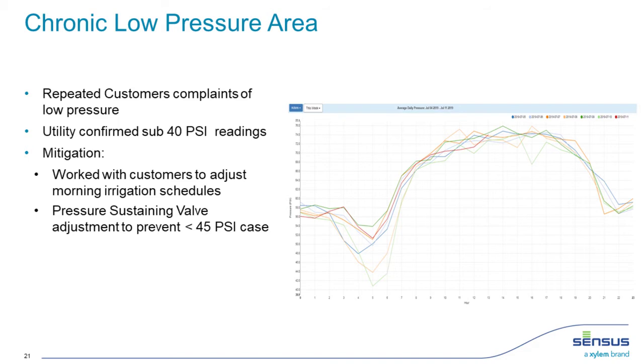What we were able to do to mitigate the issue was, first of all, to speak to a lot of the customers in that area. They had quite a few of their irrigation clocks set at the exact same time, and it turned out that their timing was the same as another large customer that watered many acres at the cemetery. So it was just quite a demand at the same time. We were also able to check out another pressure sustaining valve nearby and make some minor adjustments to prevent pressures from dropping below 45 PSI in this area.